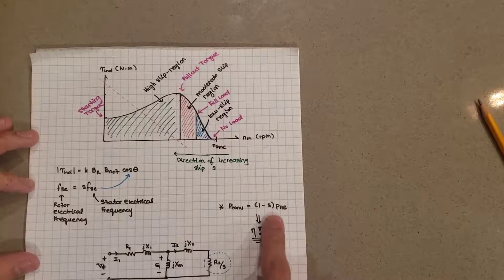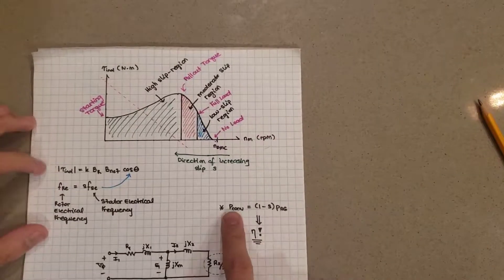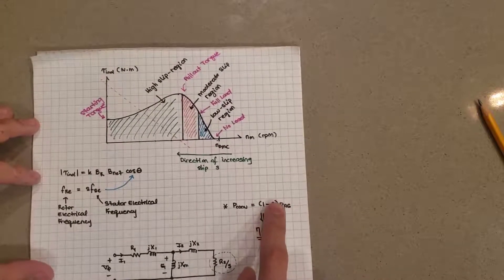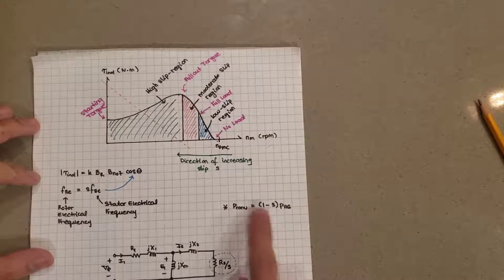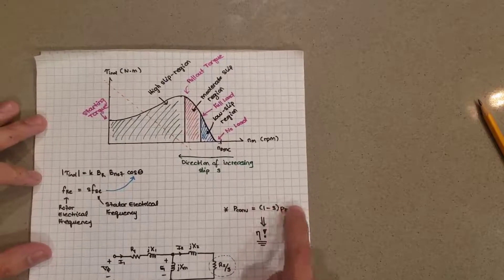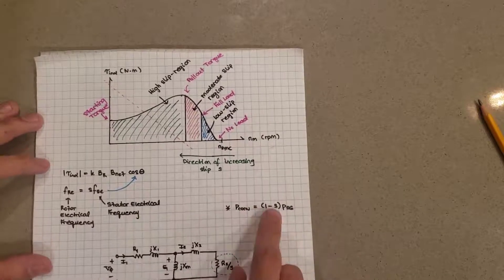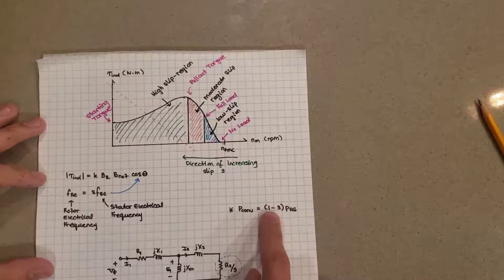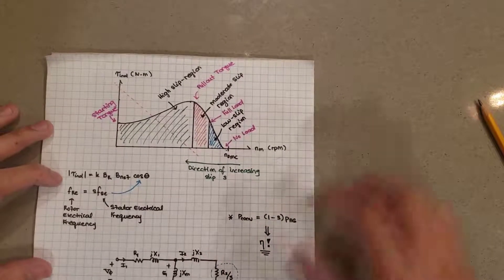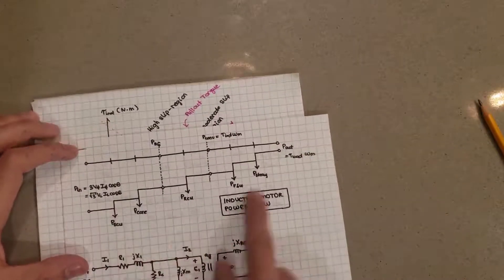What does that kind of say? That tells you that the amount of the air gap power present that is converted into mechanical power is equal to 1 minus the slip ratio. So you can imagine if you have a high slip ratio, if you're operating at a high slip ratio, let's say 0.9, and 1 minus 0.9, 0.1, you're getting only 10% of that air gap power is being converted into actual mechanical power. Whereas if you had a small slip ratio, then say it was like 0.05, then that's 0.95 in there, so 95% of your air gap power is being converted into mechanical power.